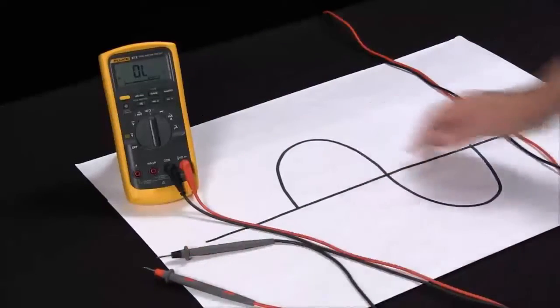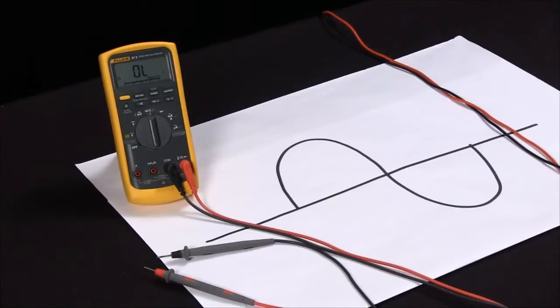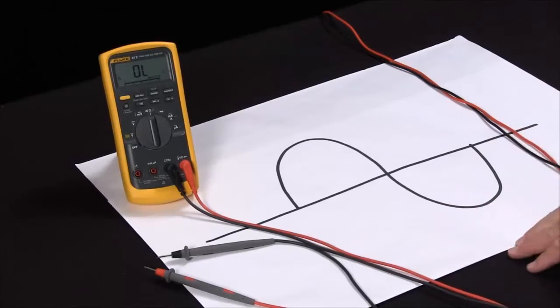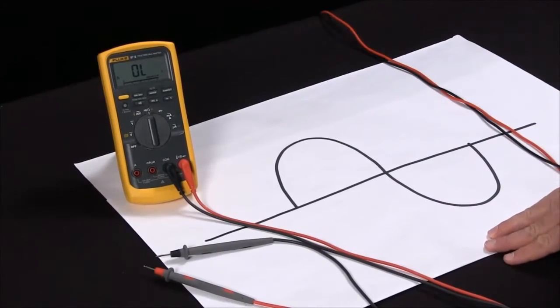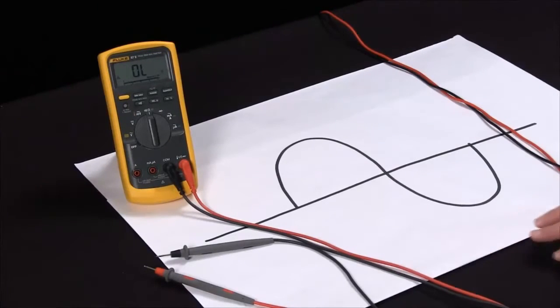Another good use for the relative mode is if I want to see a voltage drop between the source and the load. I can go to the source, hit the relative mode, it goes to zero. If I then go out to the load and I read minus 10 volts, then I know I have a 10 volt voltage drop between the source and the load.